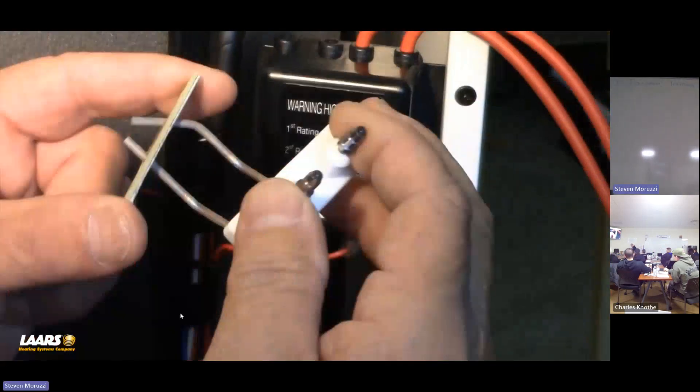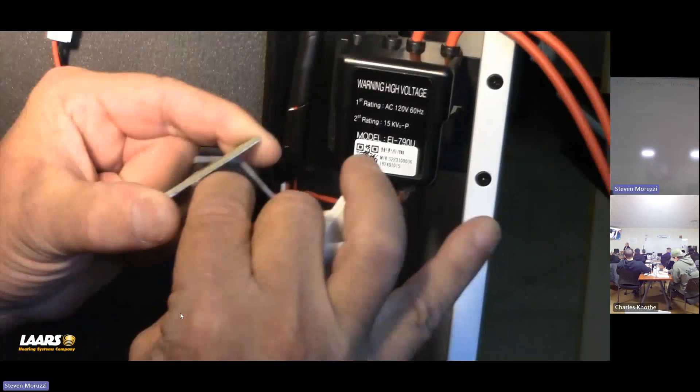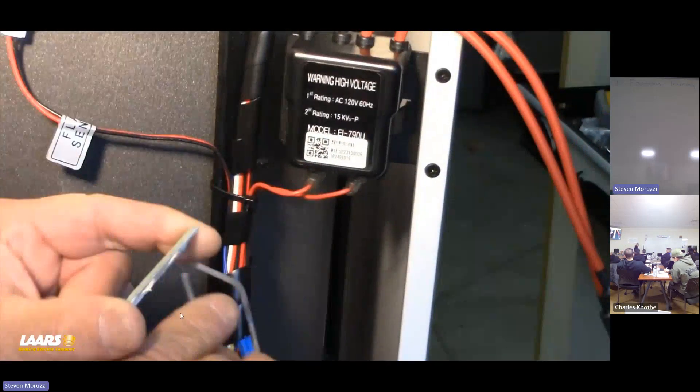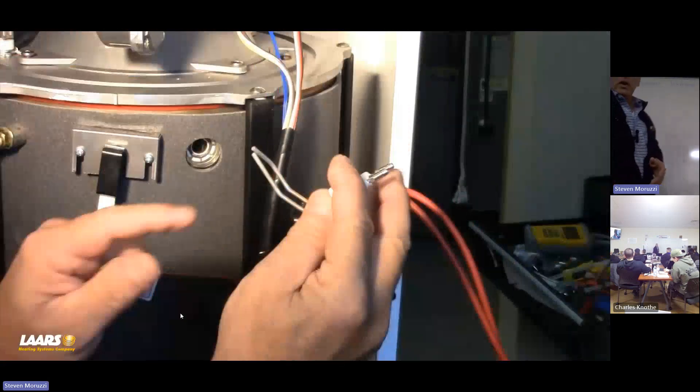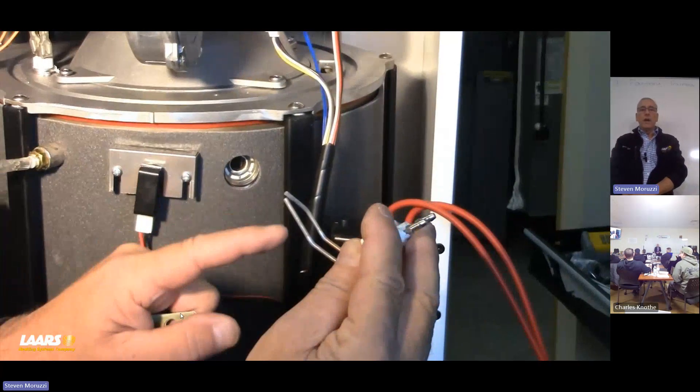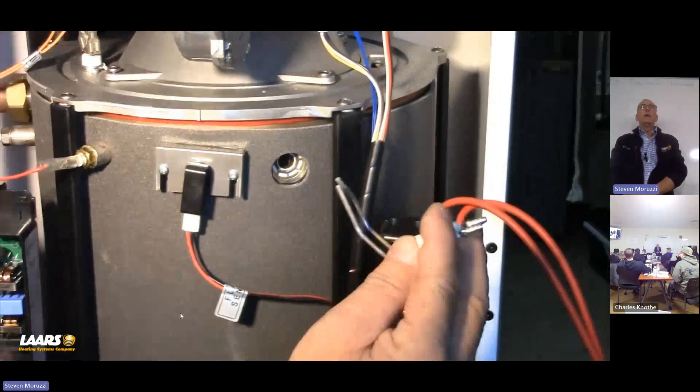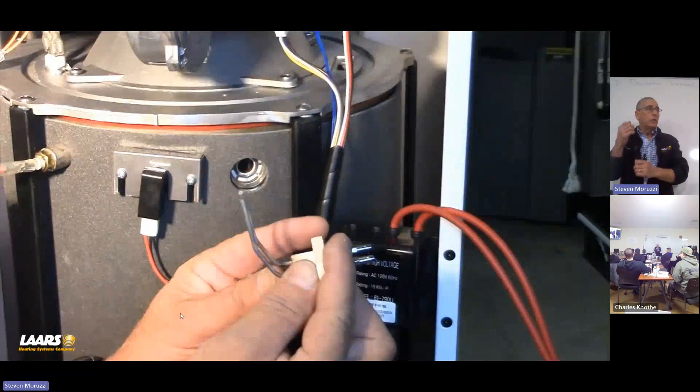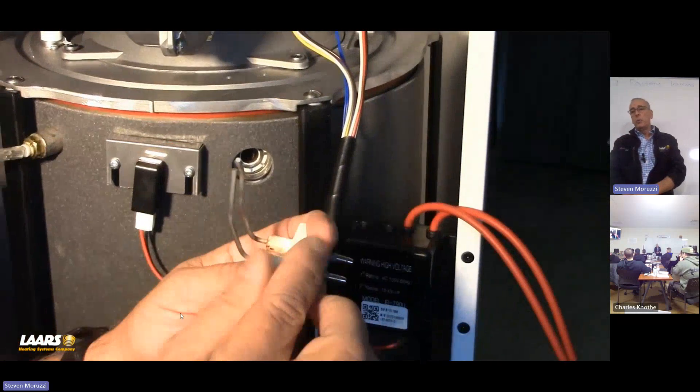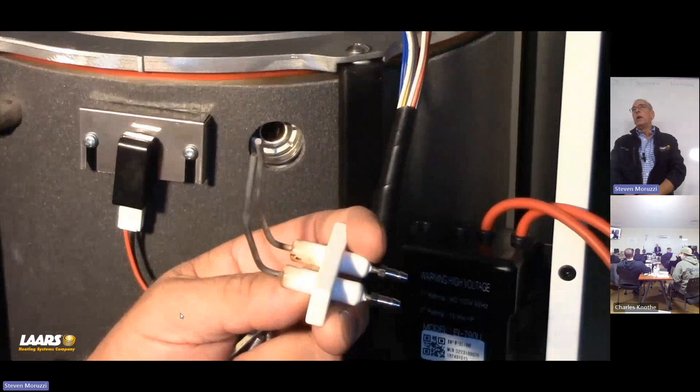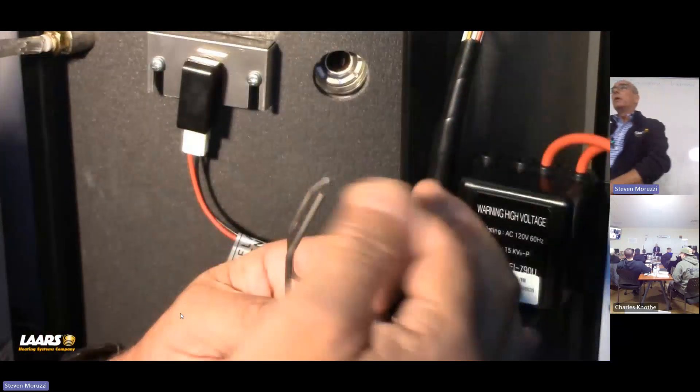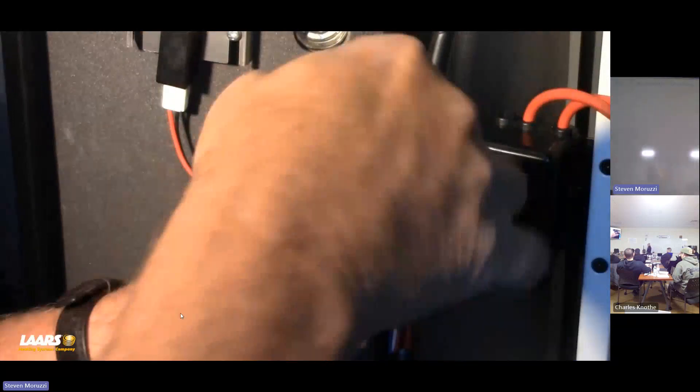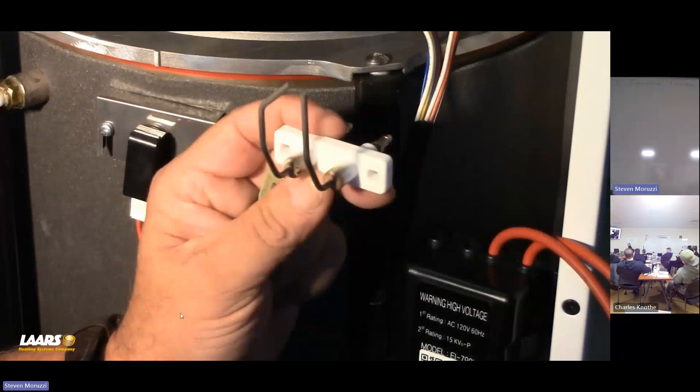Taking the igniter out and inspecting this igniter. We do give you an extra gasket. Inspect that gasket if it's broken, replace it. Here is your igniter. You want to check your gapping and clean it. To clean these, all you need is a rag. A dollar bill works. You can even use your hands. Don't use sandpaper or we're going to leave grooves in those igniter rods. Why? That's sitting in corrosive environment, corrosive environment of flue gases. That will rust up and corrode on you as well.